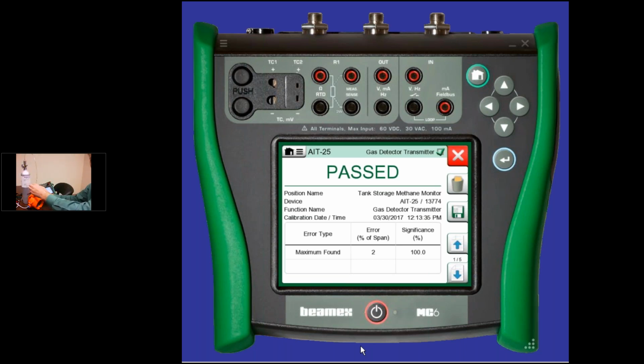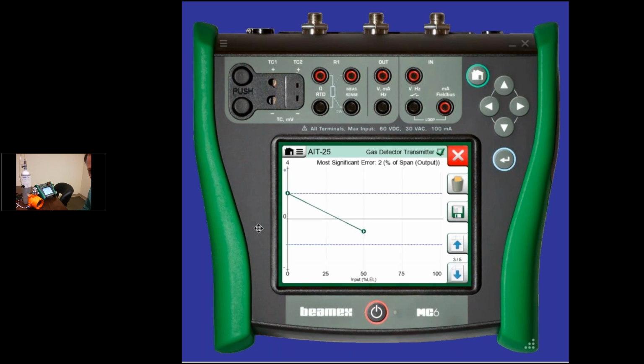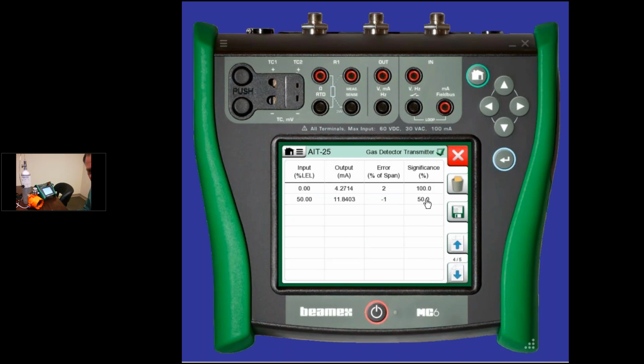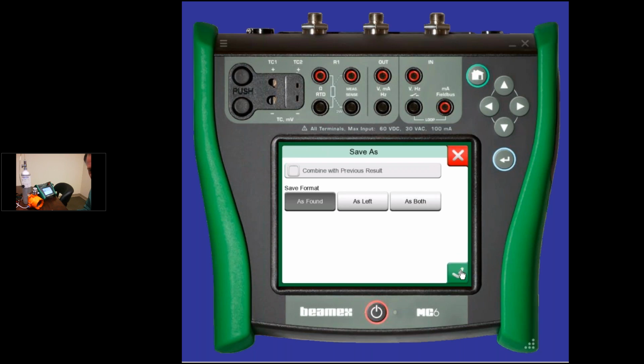And in fact, I want to go back to 0, so I'm going to remove the little cup here so that my sensor has a chance to get back to 0% quicker. But it did pass, although barely, and it's got my name in there. But there's the graph that we just saw. So we're going to actually do a calibration and trim this guy. So it was halfway out at full scale and was all the way out at 0. So let's go ahead and save this test as the as found.